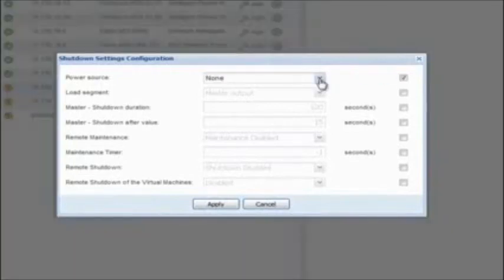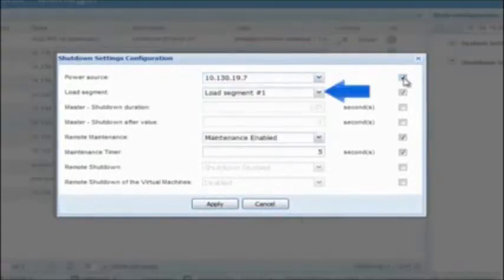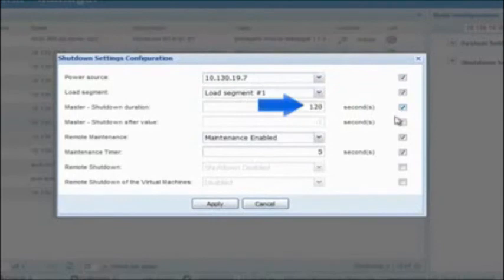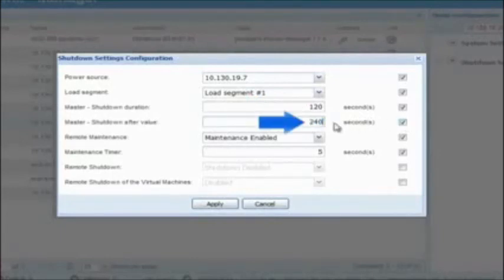Power Source: select the IP address of the UPS which powers your host. Load Segment: designate the output receptacle which the host node is connected to on the UPS — typically this will be the master segment. Master Shutdown Duration: enter the maximum amount of time in seconds needed for the host to fully complete the migration and shutdown process with vMotion. The virtual machines will shut down first and then the host. Once the designated time expires, the UPS load segment will de-energize. Master Shutdown After Value: enter an amount of time in seconds which will dictate the length of time IPM will have before it triggers the shutdown of the host.